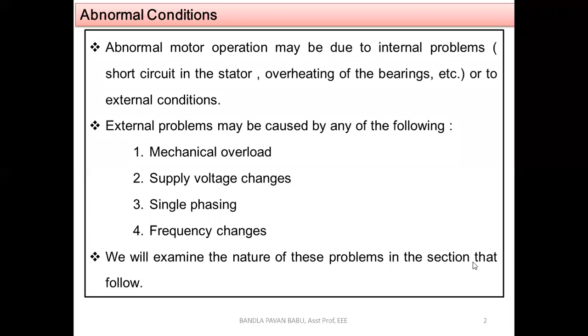According to the national standards, a motor shall operate satisfactorily on any voltage within plus or minus 10% of the nominal voltage, and for any frequency within plus or minus 5% of the nominal frequency. A small correction is that this data is taken as per the textbook, but the standards have now changed. The permissible voltage level is now plus or minus 5%, and for frequency it is plus or minus 0.5 hertz.